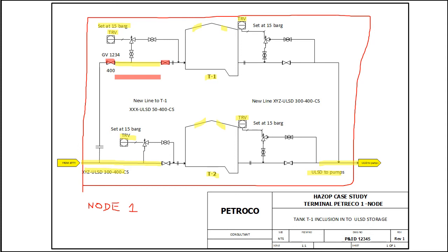Usually, if it's a substantial above ground section, it can, during the heat of the day, build up a great deal of pressure, and if it reaches the design pressure of the pipe and exceeds it, it can rupture. So therefore we set the TRV at a pressure below the design pressure of that piece of pipe.